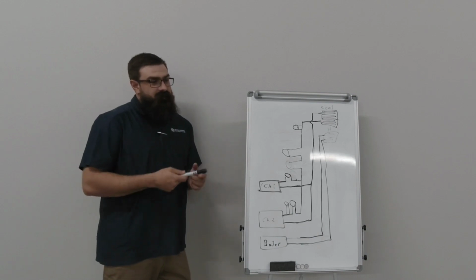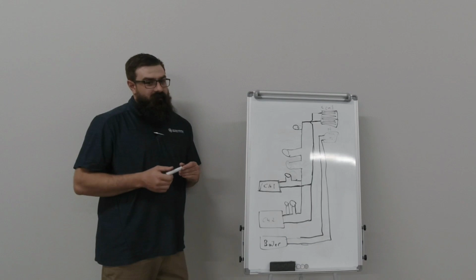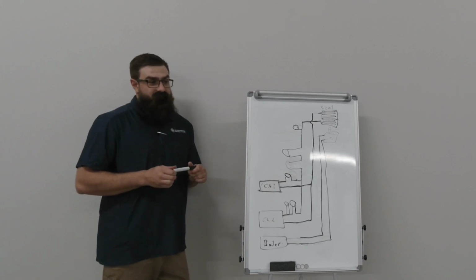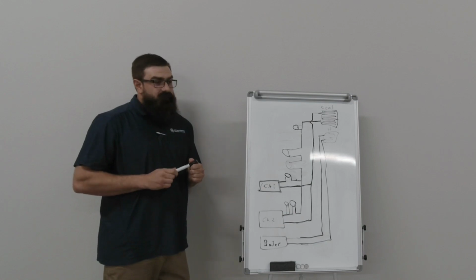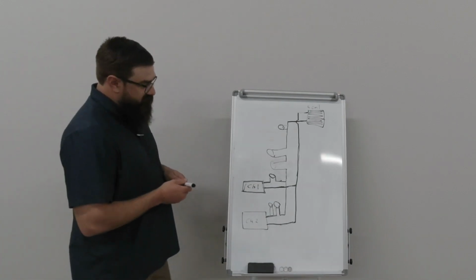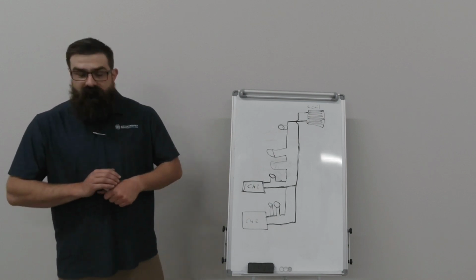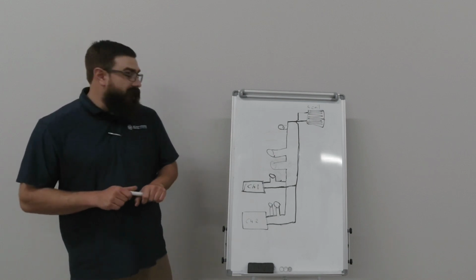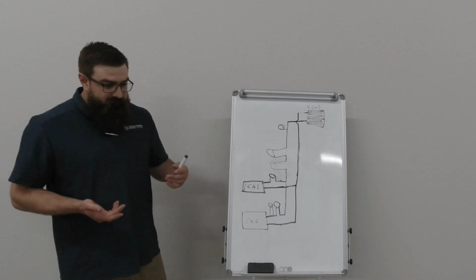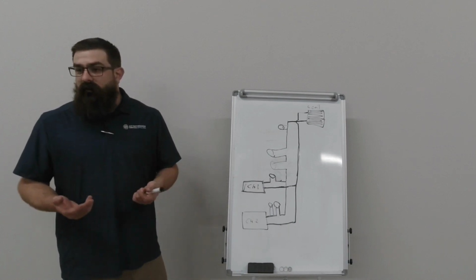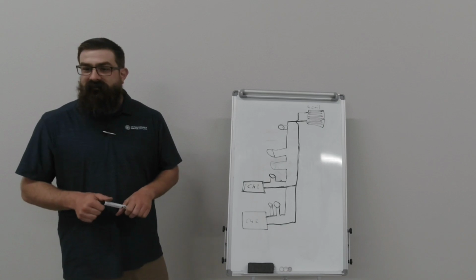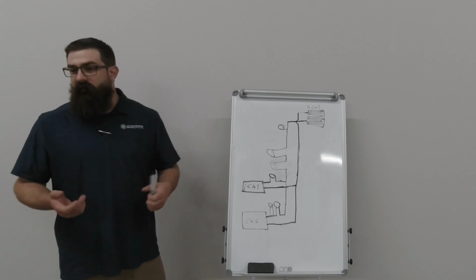In Houston, we did a building that had a large parking garage, and then between the parking garage and the tenant space above it was their mechanical. We'll stick with chill water just because chill water and hot water can all be plumbed the same way. It's really 6 of one, half dozen of the other as far as that. Typically your chill water is always going to be larger than your hot water.